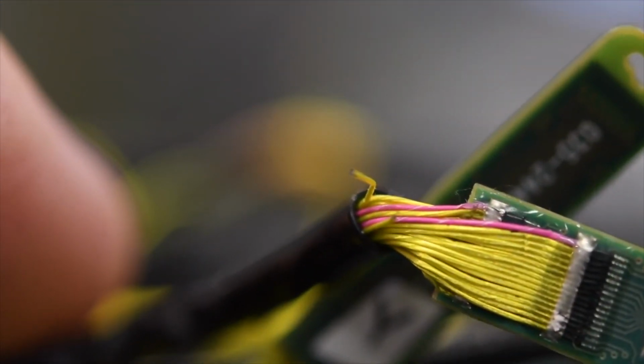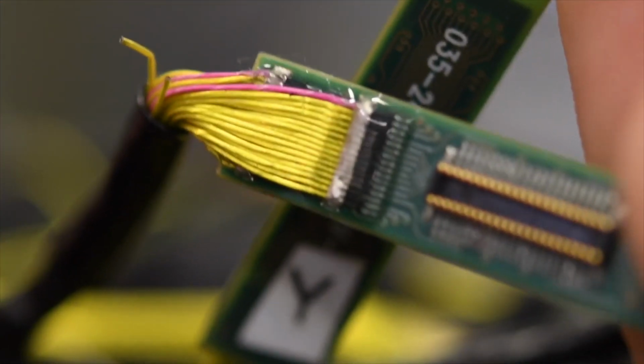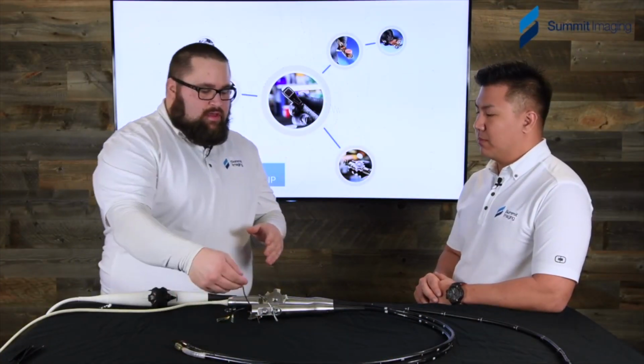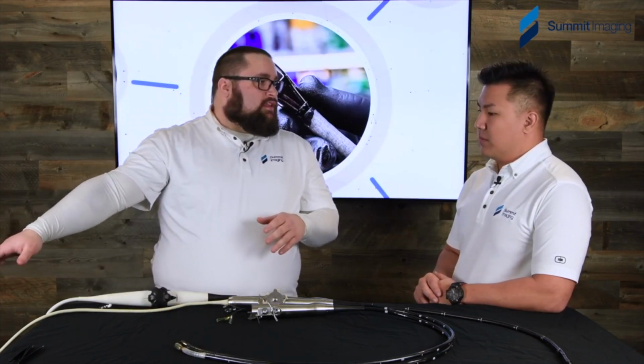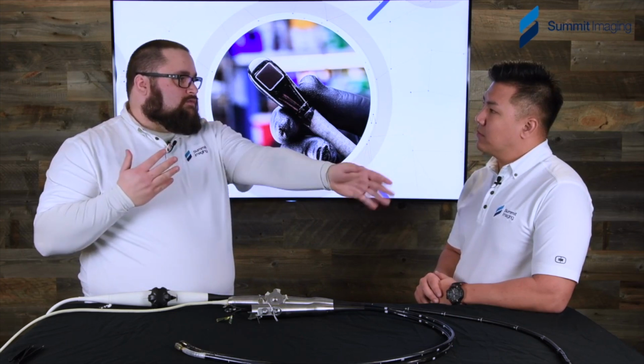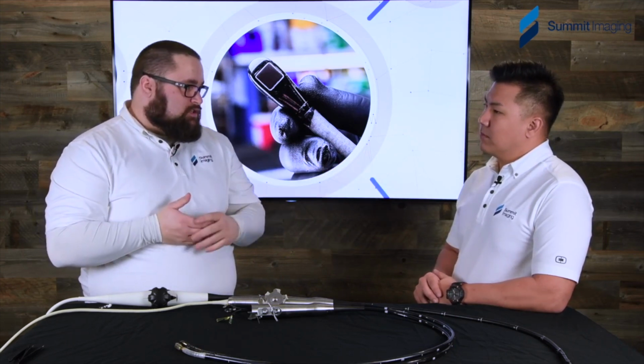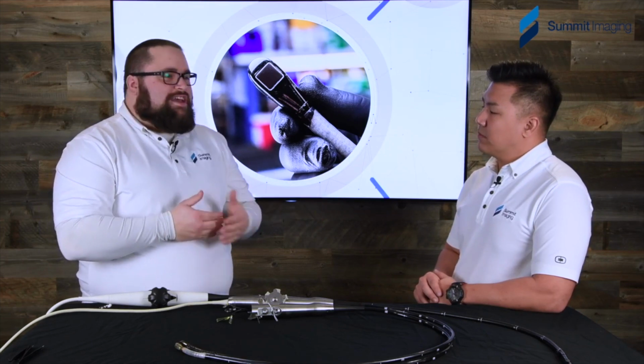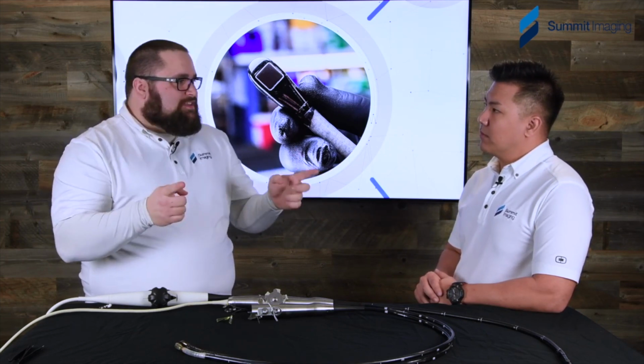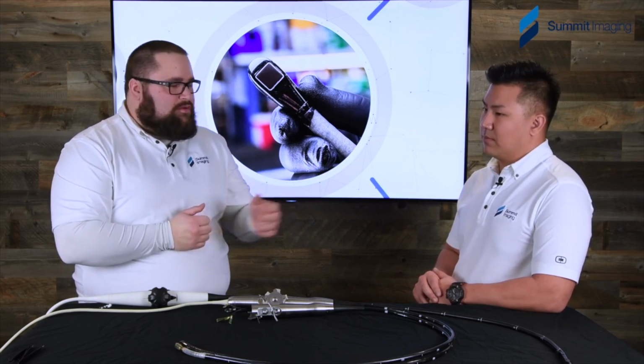Well, and you can spend a lot of time chasing a problem too. Say you have a spike. A spike can be caused by two lines chafing on each other. Now that can be in the tip, that can be in the handle, that can even be back in the can that we're going to talk about in a moment too. There are yards of line for each channel inside these transducers, and you have a few connectors, a few kind of halfway points where you can isolate it and see if the signal's going through clean there.